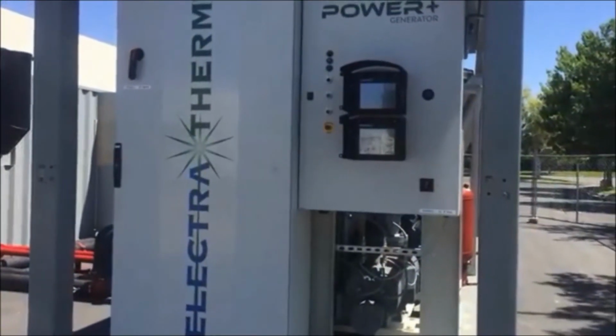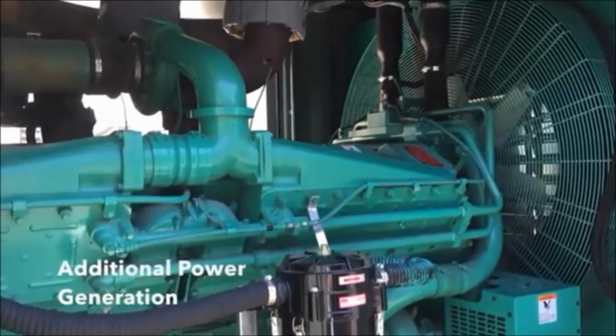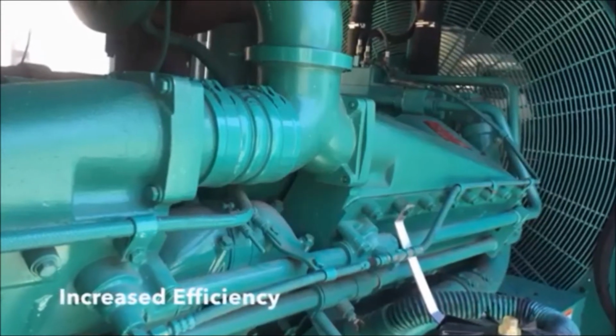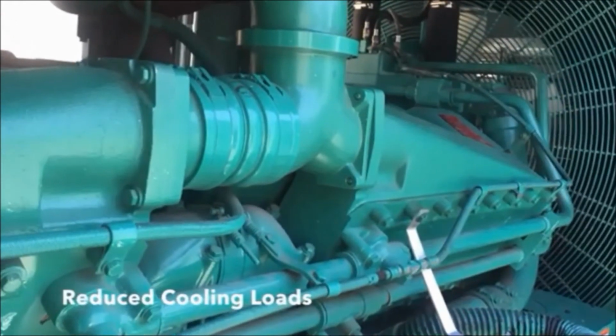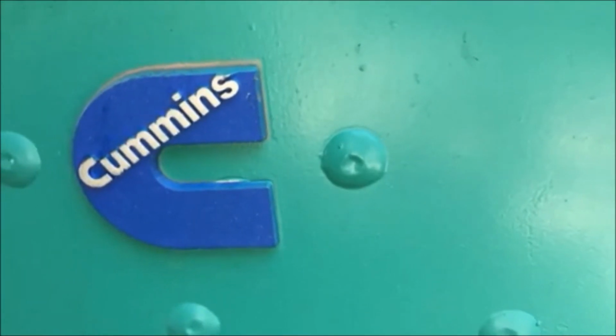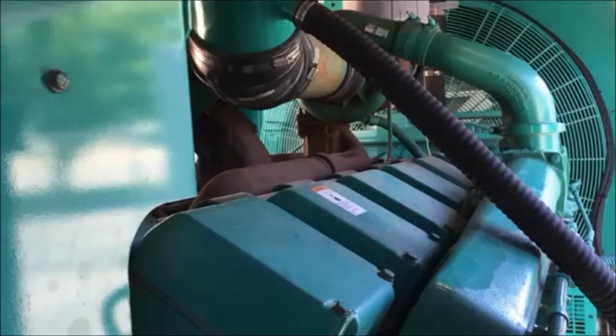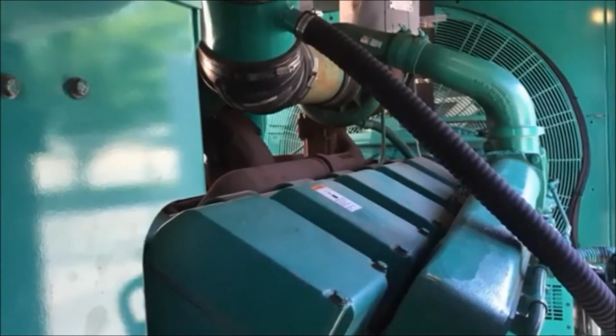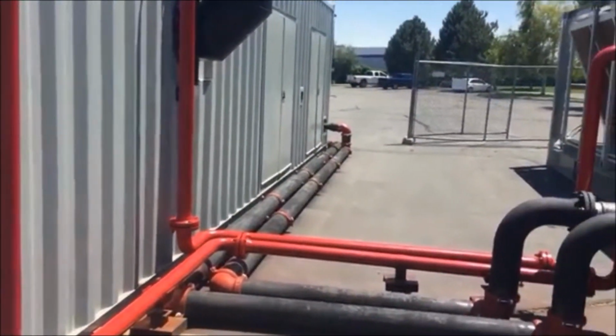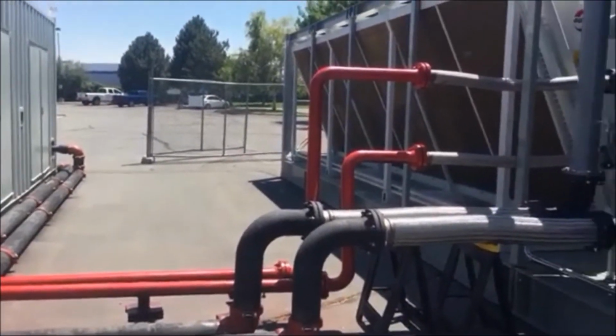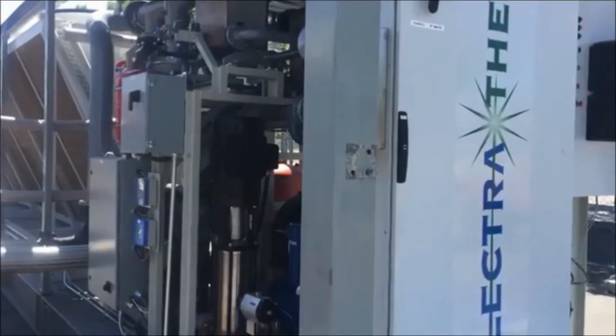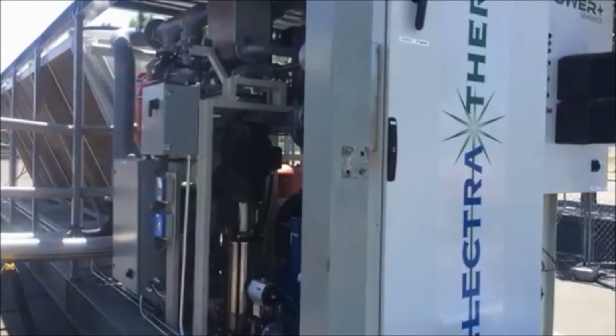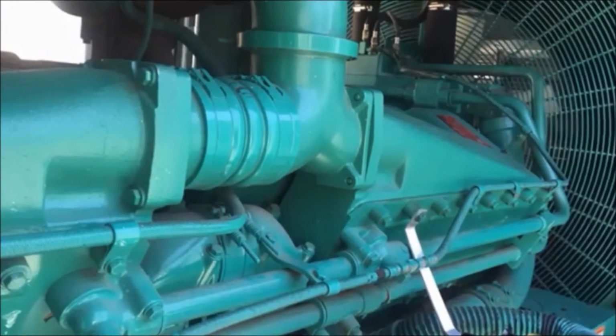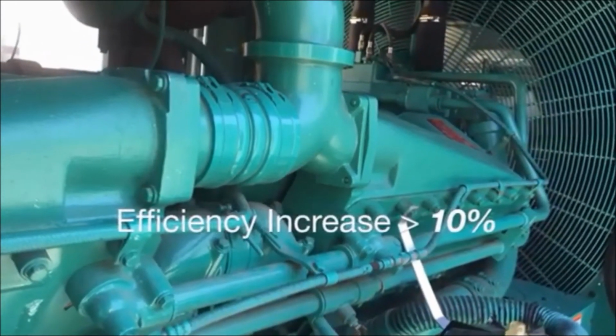When replacing the radiator for the engine with an ORC, the technology benefits include additional power generation, increased efficiency, and reduced cooling loads. The Cummins engine originally required a 56 kilowatt parasitic load for cooling, enough power for 30 homes. Instead, the heat goes to the Power Plus, where it generates an additional 60 kilowatts of fuel-free, emission-free electricity. In total, this model of a Cummins engine achieved an efficiency increase over 10%.